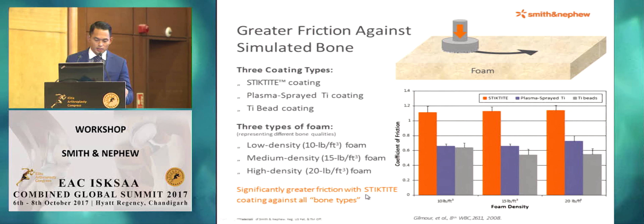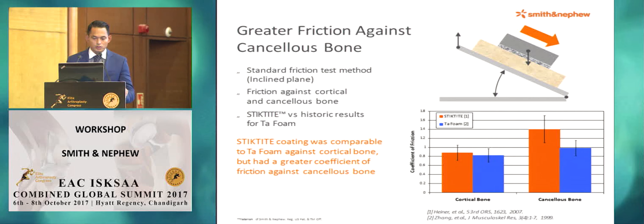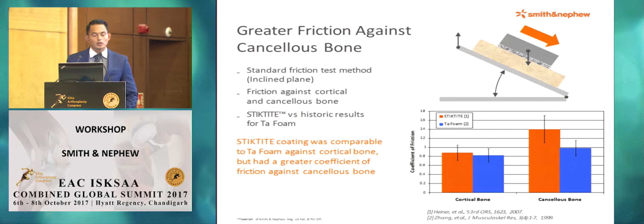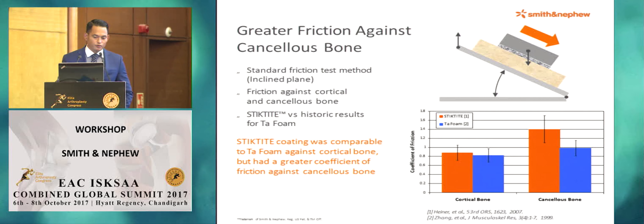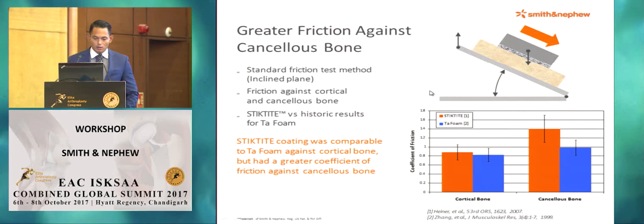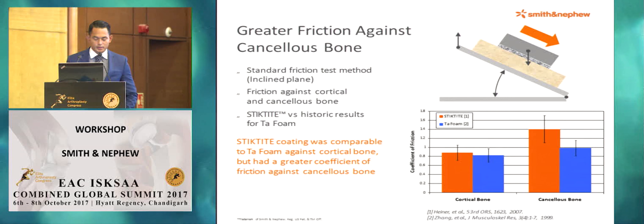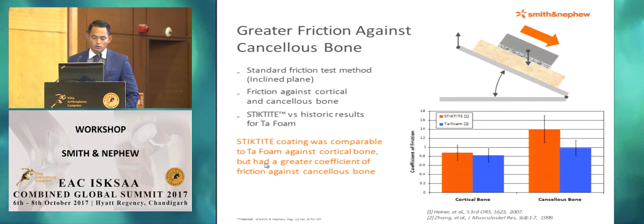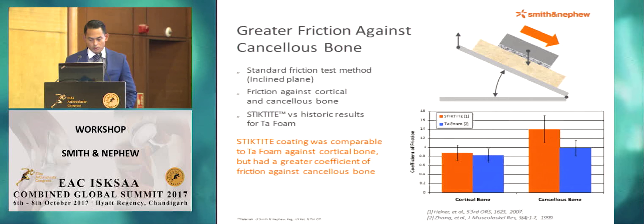Significantly greater friction was seen with STIKTITE across all bone types. With regards to friction against cancellous bone — which is what we want in total hips, as we're getting down to bleeding cancellous bone — using the standard friction test method along an incline plane, friction was tested against cortical bone as well as cancellous bone, and STIKTITE was compared to historic results for a tantalum foam. STIKTITE coating was comparable to tantalum foam against cortical bone, but had a greater coefficient of friction against cancellous bone — very important, as we're primarily going against cancellous bone when putting in our cups.